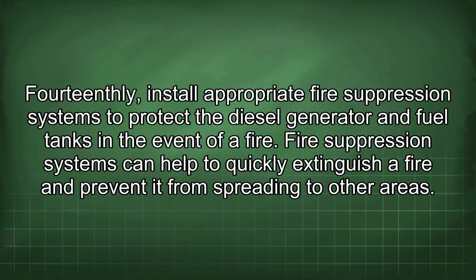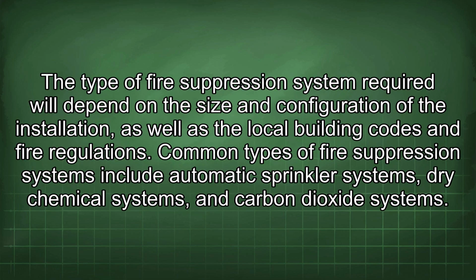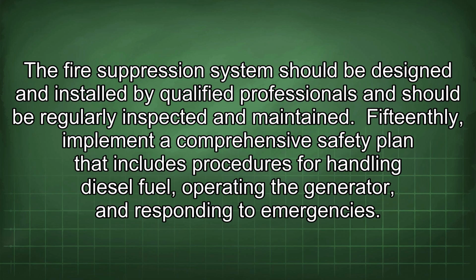The ventilation system should be designed to effectively remove vapors from the area and should be regularly inspected and maintained. 14thly, install appropriate fire suppression systems to protect the diesel generator and fuel tanks in the event of a fire. Fire suppression systems can help to quickly extinguish a fire and prevent it from spreading to other areas. The type of fire suppression system required will depend on the size and configuration of the installation, as well as the local building codes and fire regulations. Common types of fire suppression systems include automatic sprinkler systems, dry chemical systems, and carbon dioxide systems. The fire suppression system should be designed and installed by qualified professionals and should be regularly inspected and maintained.